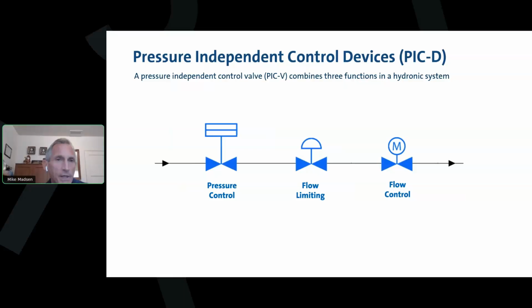So the latest and greatest with valve technology, which we're saying we should go to away from these valves, is pressure independent control valves. It's the latest and greatest valve out there. Basically, what a PIC-V does is it combines all the functions of the other valves into one valve. So it's doing pressure control, it's doing flow limiting, and it's also doing flow control through the air handler unit. So whether you're using pressure dependent or pressure independent, we're going to have all these functions. The pressure independent is just a way to do it all with one valve.